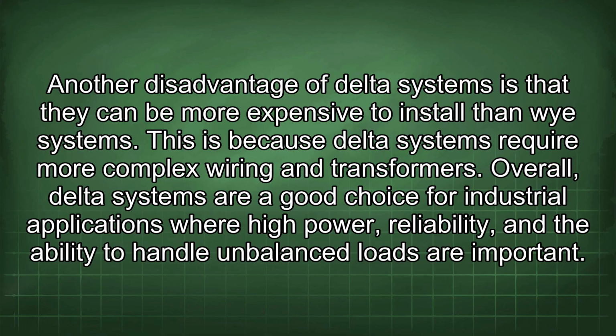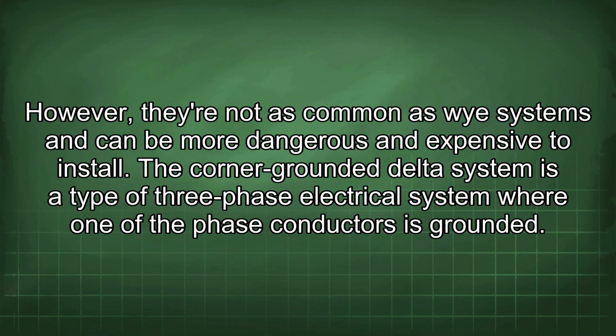Overall, delta systems are a good choice for industrial applications where high power, reliability, and the ability to handle unbalanced loads are important. However, they are not as common as Y systems and can be more dangerous and expensive to install. The corner-grounded delta system is a type of three-phase electrical system where one of the phase conductors is grounded.